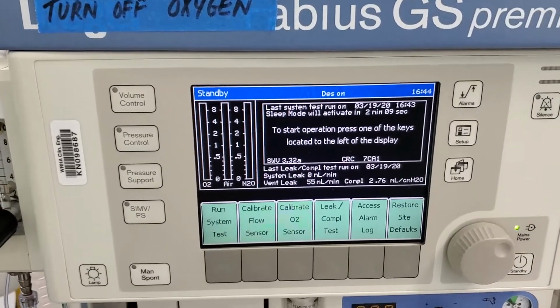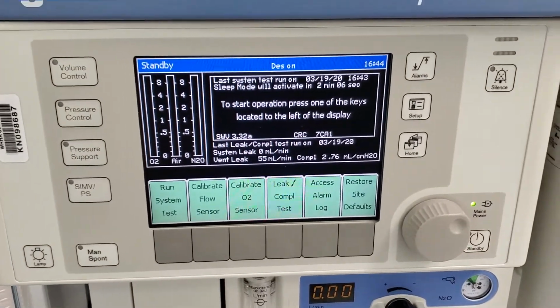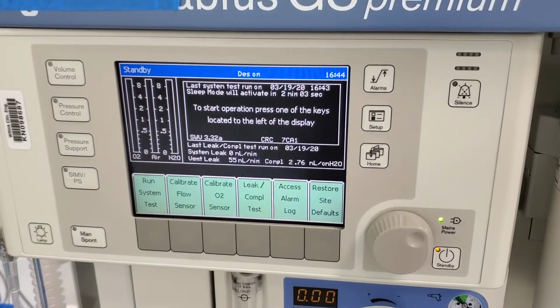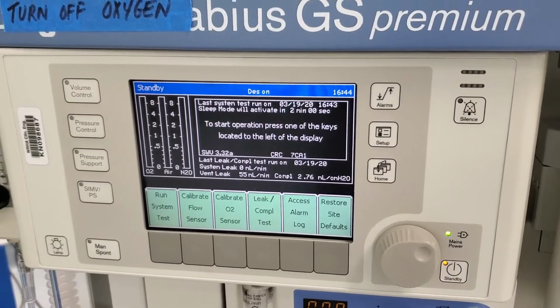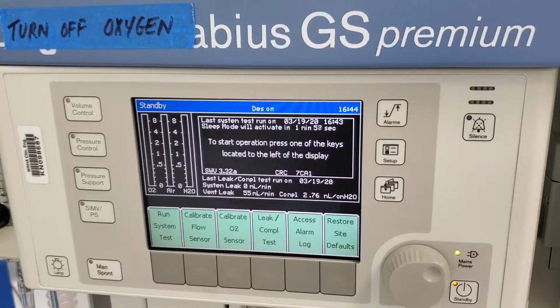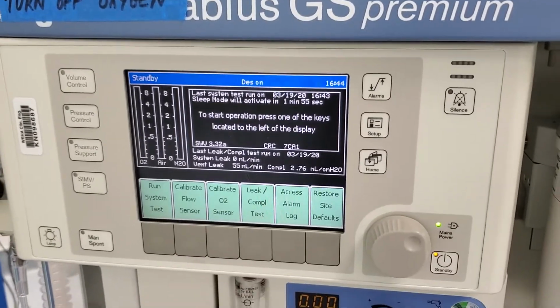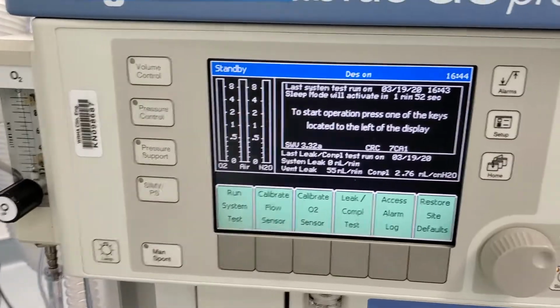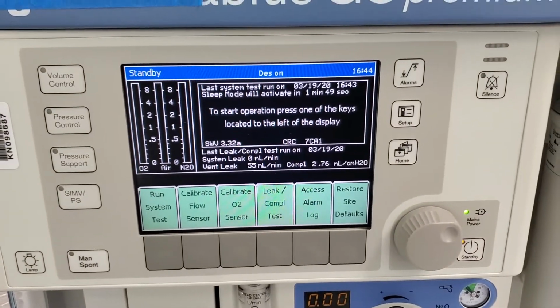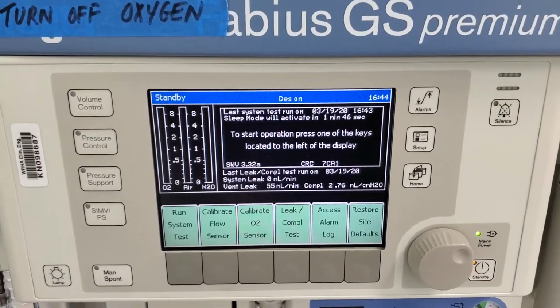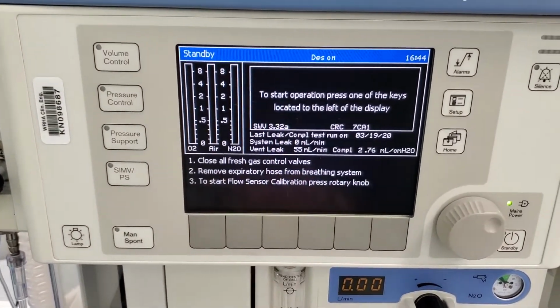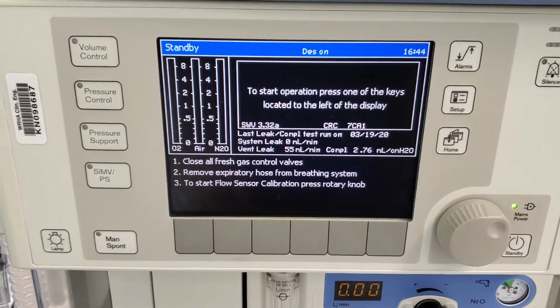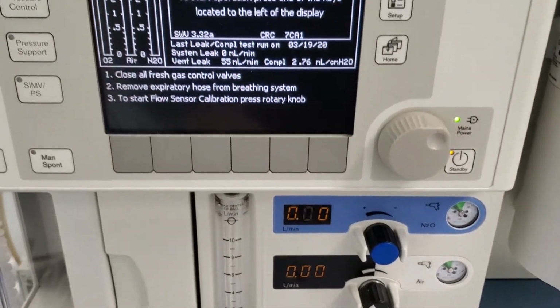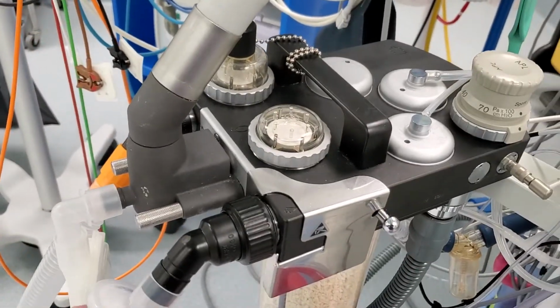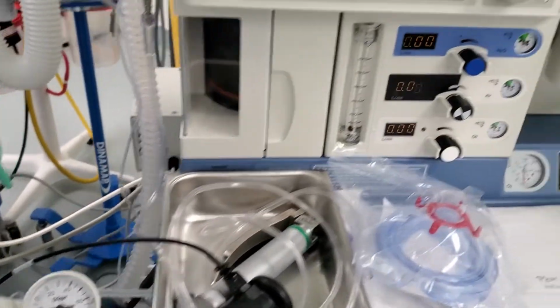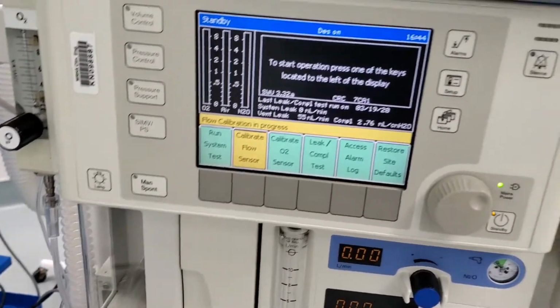Something that could be conditionally functional was, say, the backup battery didn't charge enough, and that is just warning you that it didn't charge, and you have to acknowledge that before you can actually use the ventilator. This machine has 2 sensors that need to be calibrated every 18 hours, so once per shift usually. The first is the flow sensor, so we just push the button. It gives you instructions on how to go about with the test. We want to make sure that our flows are all off. We remove the expiratory hose from the machine, and then we push the knob to start the flow sensor calibration.